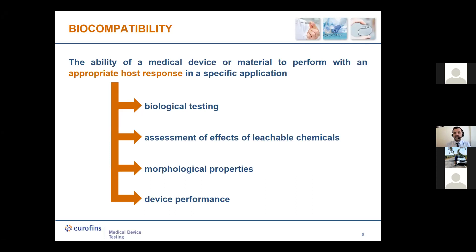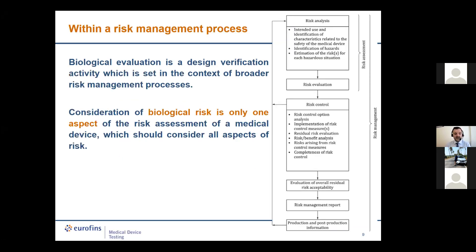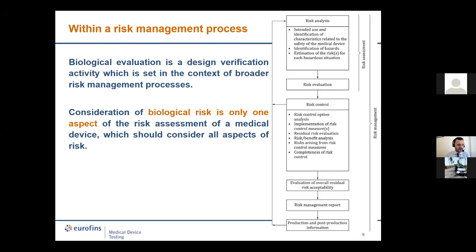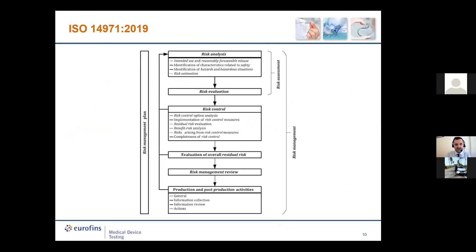Biological evaluation is a design verification activity set in the context of the broader risk management process. The flow chart in ISO 10993-1 shows that consideration of biological risk is only one aspect of the overall risk assessment. Biological risk is a small — though not trivial — part of the overall risk management of the medical device. The same generic flow chart appears in ISO 14971 of 2019, where there is a clear indication of the need for a plan.